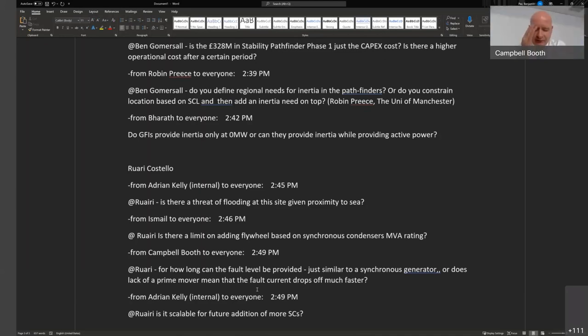And I suppose just another question for me, in terms of the protection side of things, and again, quite a naive question. If you've got a machine with a set of inertia, but in this case it's not, I know that motors will generate fault current sometimes. But when you mentioned the short circuit level, is the envelope, you normally get that sort of subtransient reactance driven peak, and then over a few cycles it starts to reduce. Is that significantly different because there is no prime mover, no steam turbine or something with its power going into it, even though you might not be able to extract much real power during a close-up short circuit?